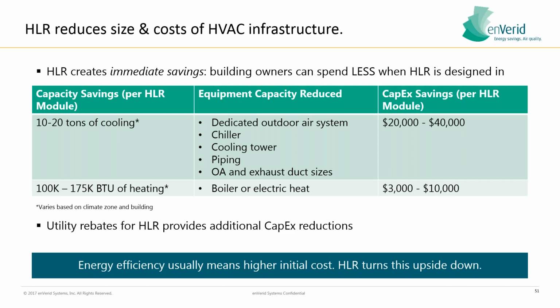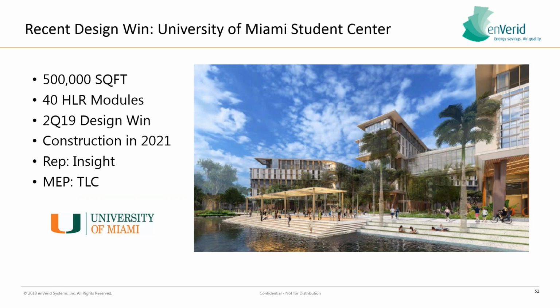Here's an example of a tonnage reduction. Where are you achieving these first cost savings? Dedicated outside air systems can essentially be turned into packaged rooftop systems if you're reducing outside air significantly enough. Chiller sizing can come down. ERVs can be eliminated or greatly reduced. And various duct sizes can also be shrunk. We do have, as mentioned before, various HLR rebates as well for CapEx reductions. Here are some other larger scope projects that we have as well.